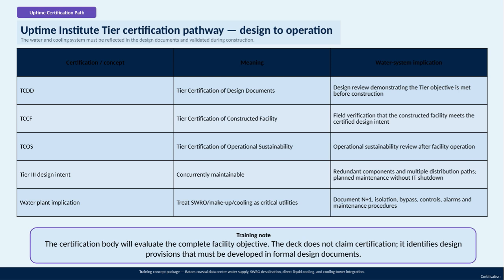Then there's TCCF, Tier Certification of Constructed Facility, which is about verifying that the facility as built matches that certified design. Finally, TCOS, Tier Certification of Operational Sustainability, reviews how well the facility is operating over time to ensure it continues to meet the standards. For a Tier 3 design intent, the facility must be concurrently maintainable.